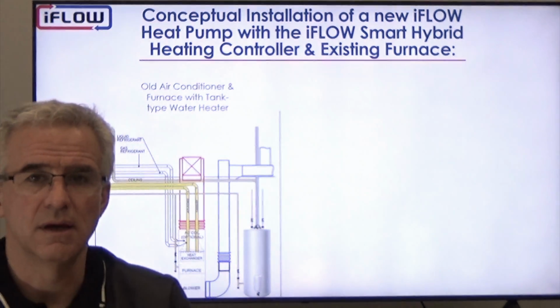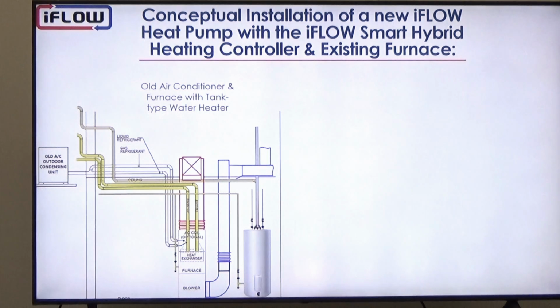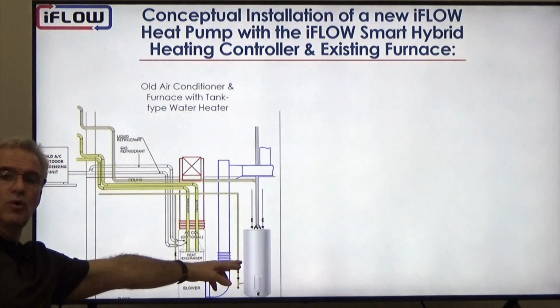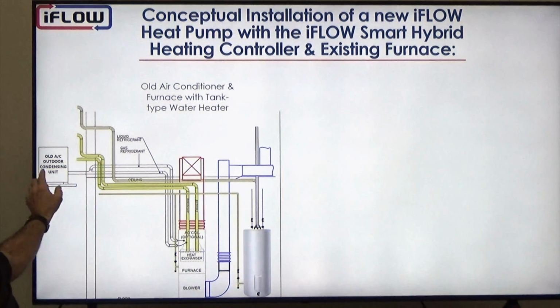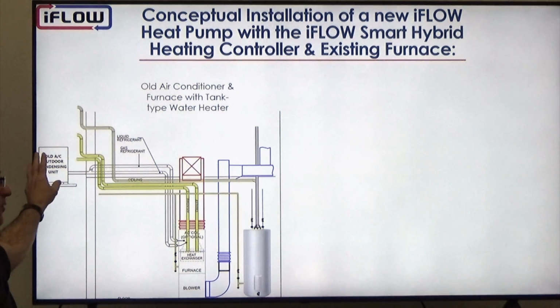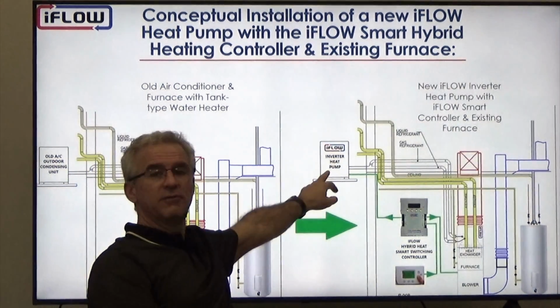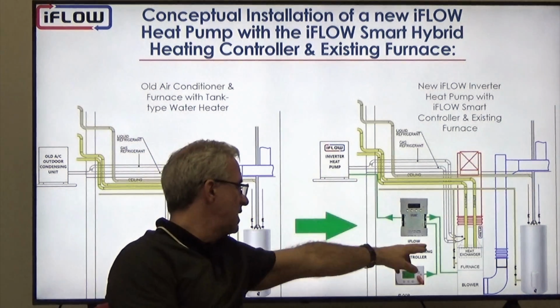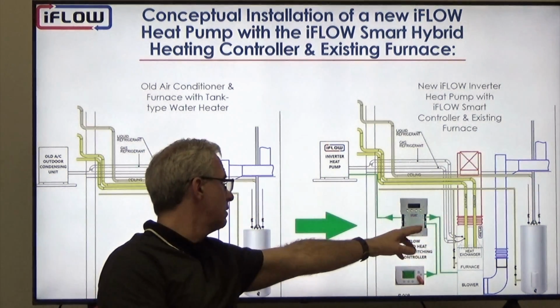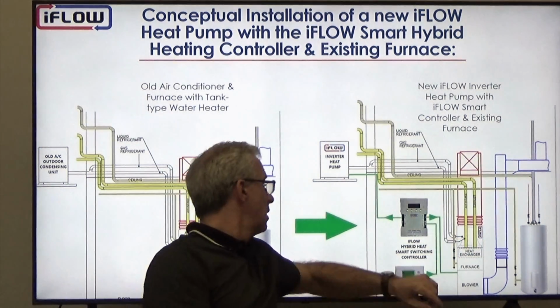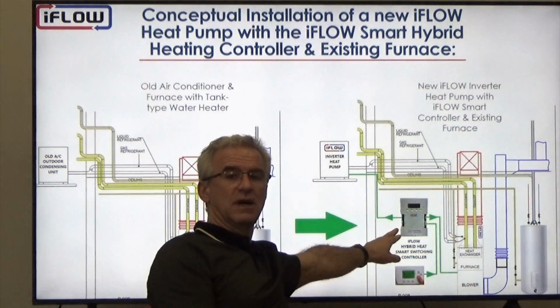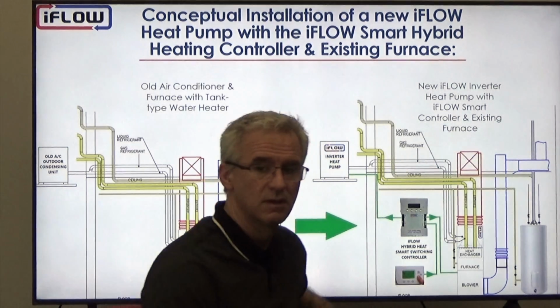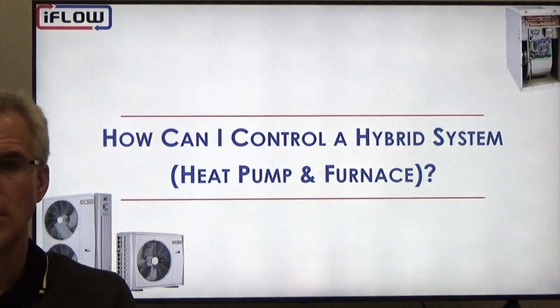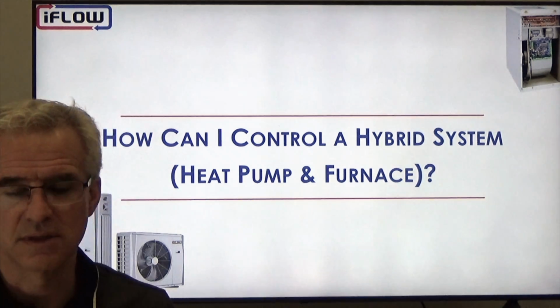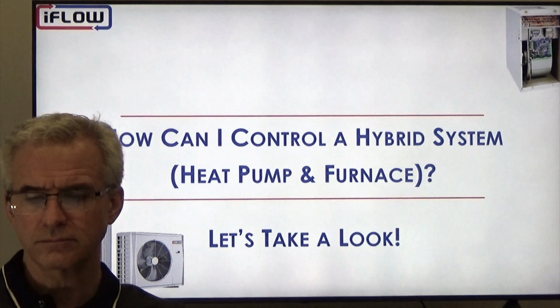So, for example, this is an installation that we would look at. In this diagram, you have an old air conditioner outside with a furnace and a tank-type water heater. In this application, what we would do is we'd switch the old air conditioner out for a new iFLOW heat pump, for example. We put a new iFLOW inverter-driven heat pump in. We would keep the existing furnace and keep the existing tank-type water heater. But then for the switching controller, we could use a thermostat, but we can also use the iFLOW switching device. And we'll show you the advantages of using the iFLOW controller. So again, how can I control that hybrid system, that combined system? So let's take a look.